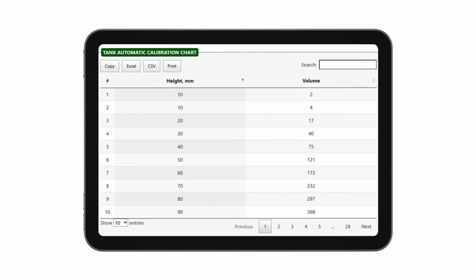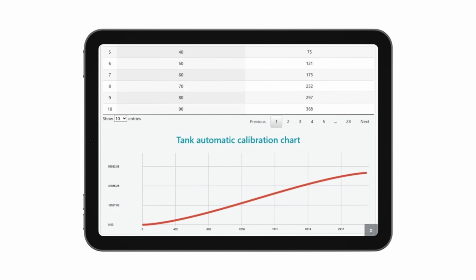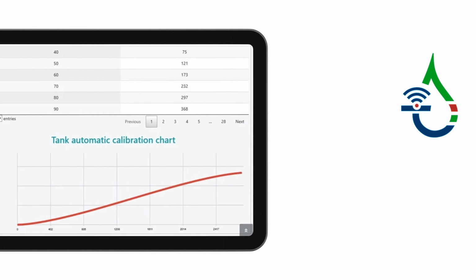Calculation and formation of tank calibration charts are performed automatically during the system operation using the results of measurements received from the ATG probes installed inside the tanks and from the fuel dispensers, which fill the fuel.